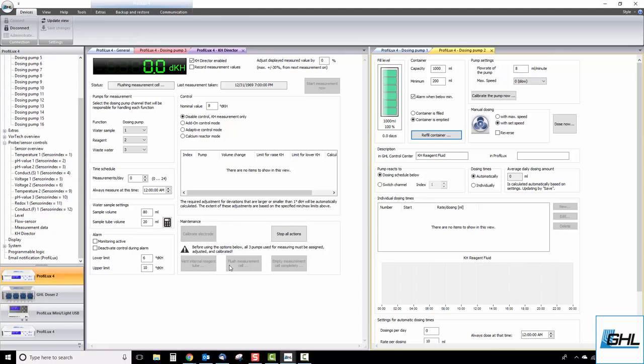If you see any leaks, click on stop all actions, then click empty measurement cell completely. Once the cell is emptied, check the compression fitting and make sure it is not loose. You can also apply some Vaseline around the rubber ring to create a better seal. Once that is done, retry the flush measurement cell step.